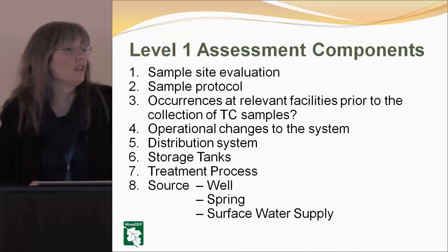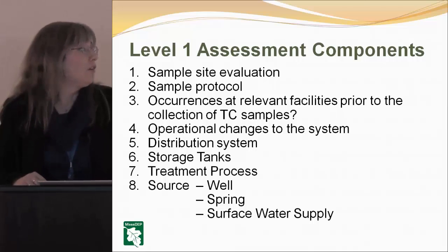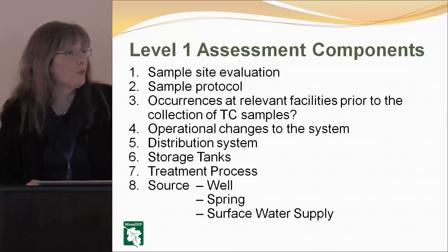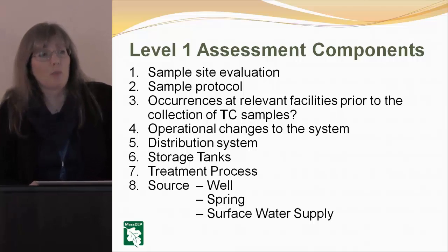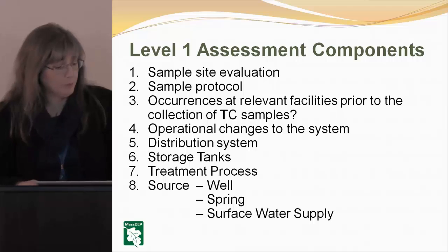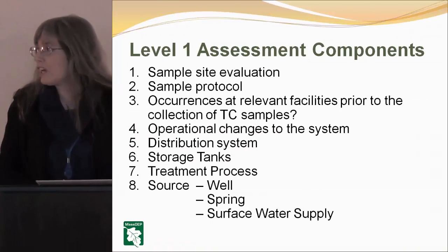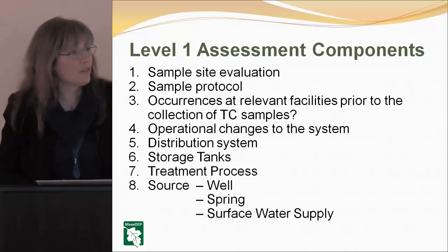Have you had a change in your flow patterns because of a removal or addition of sources or other components, tanks, things like that, or treatment processes that may change how the water's flowing through your system? Make sure you're being objective in all the different categories so you don't overlook something that could be critical that you think, well, our sampling is always fine. Well, did your guy remove the aerator? You know, the simple things like that.